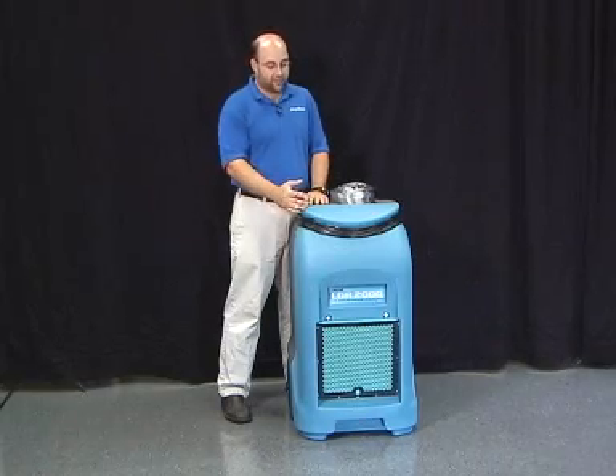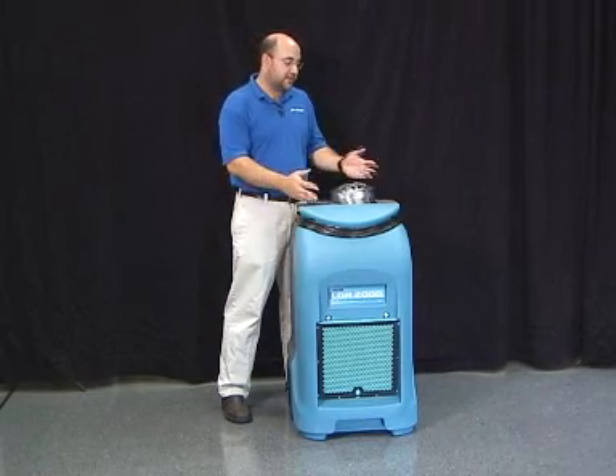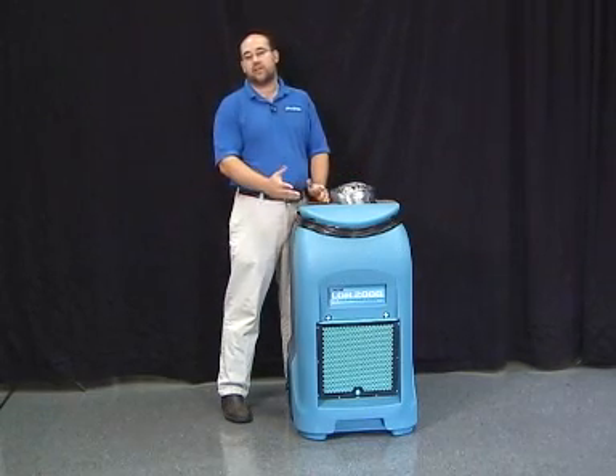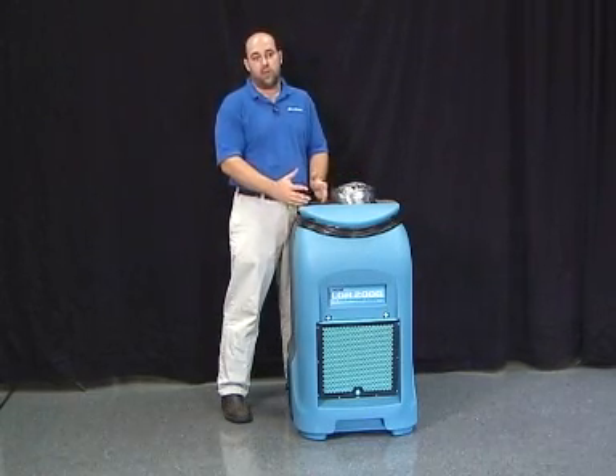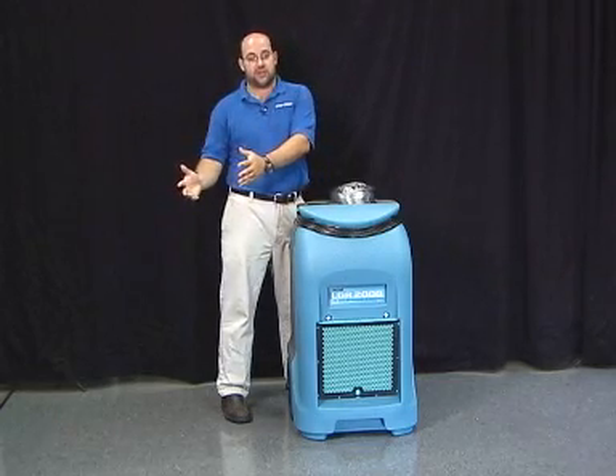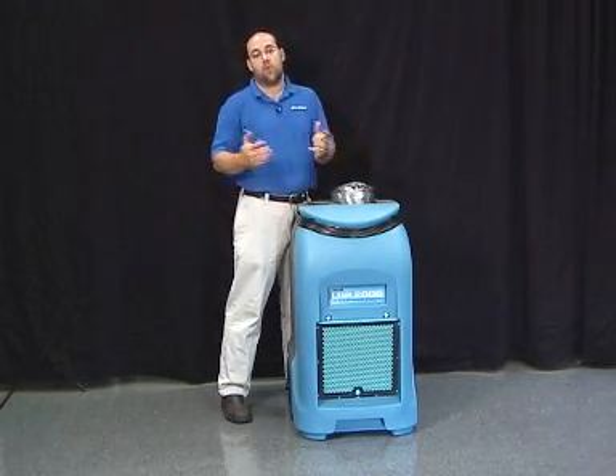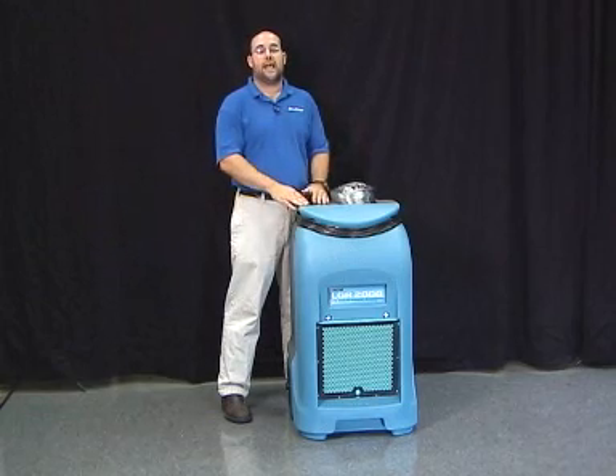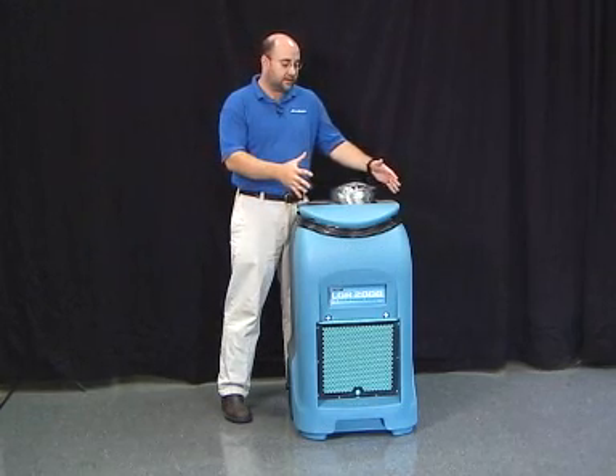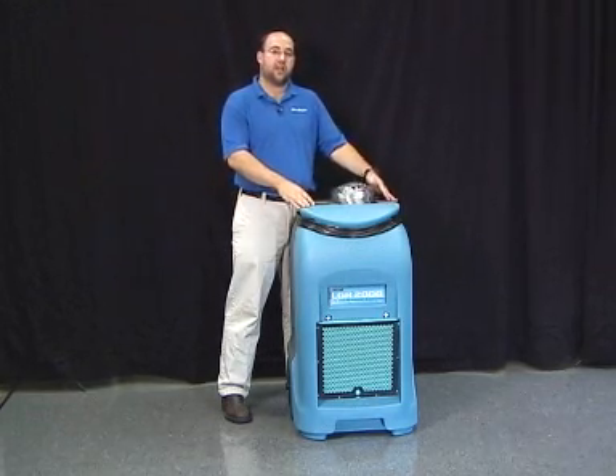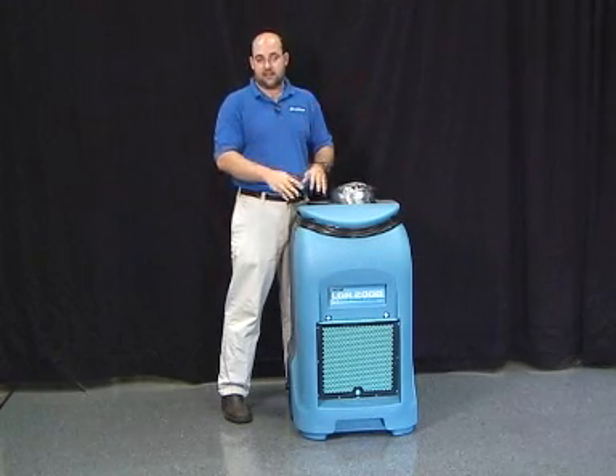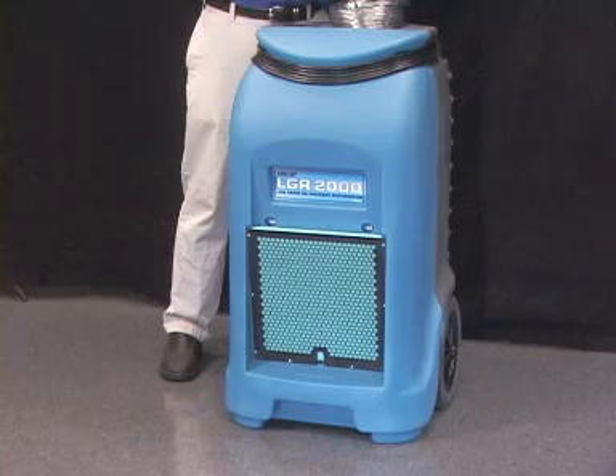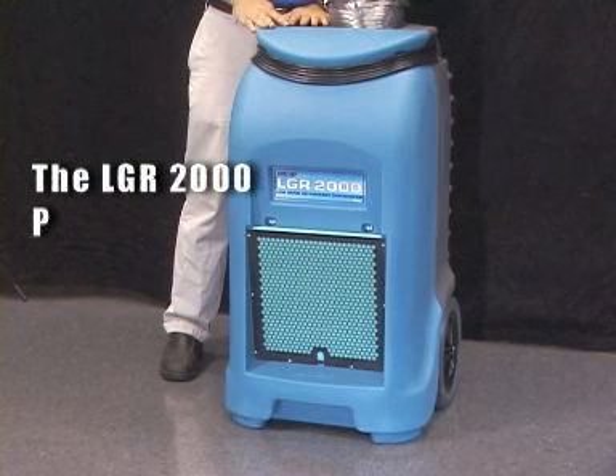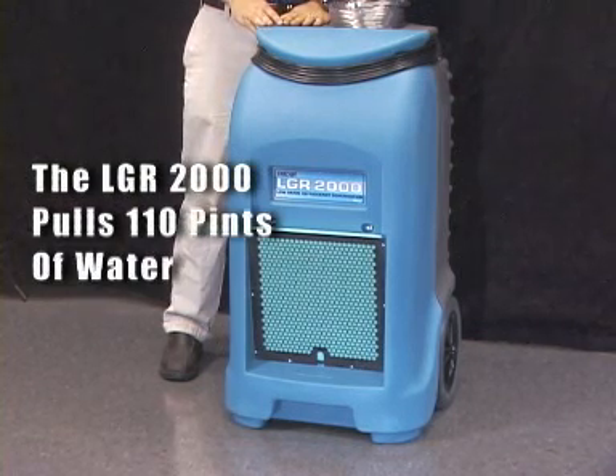Some of the features that are offered on the LGR 2000: the system has the capacity of pulling 172 pints of water. That is at what we call saturation. More realistic to a water damage job is what we call AHAM. AHAM is the system's ability to remove moisture at 80 degrees Fahrenheit, 60% relative humidity. At those conditions, the LGR 2000 will pull 110 pints.